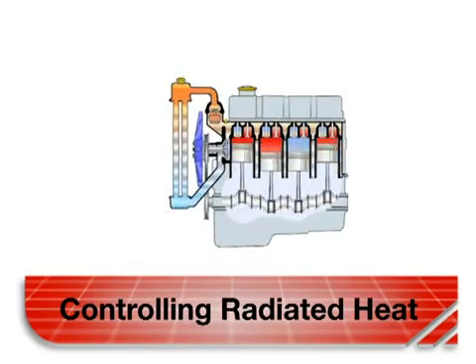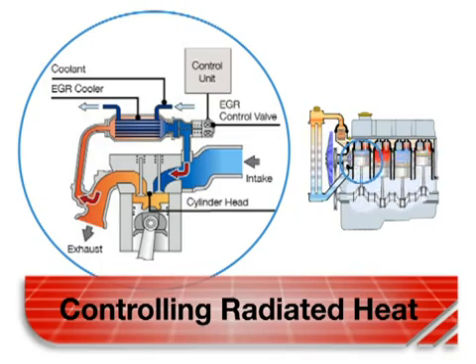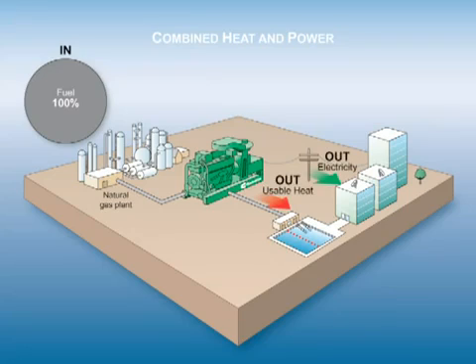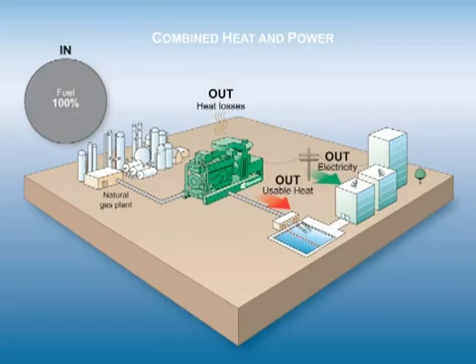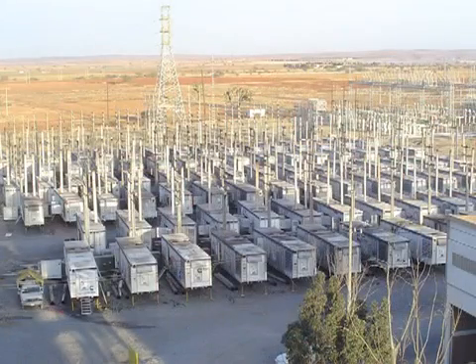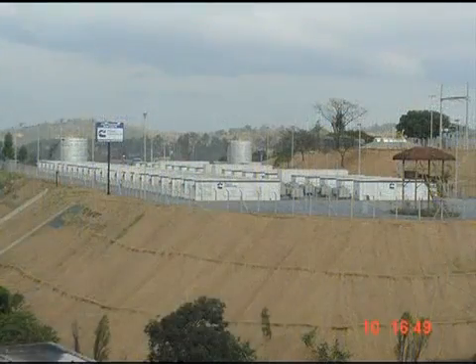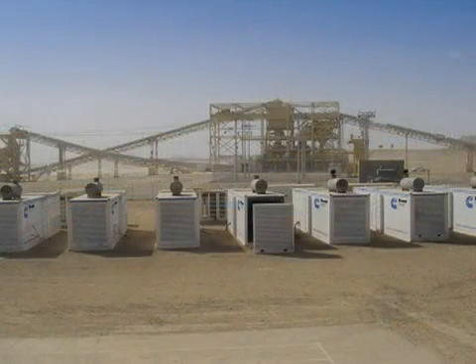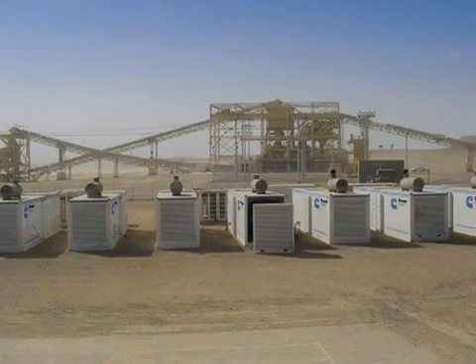To make more efficient use of the available energy, some waste heat can be recaptured. Combined heat and power, or CHP, applications make use of radiated heat. But even in these applications, a lot of heat is radiated to the surrounding air. In fact, if you have several large generator sets in one location, they can create their own microclimate from the heat they give off. This is important since the higher ambient temperature affects the air intake, which in turn affects generator performance.